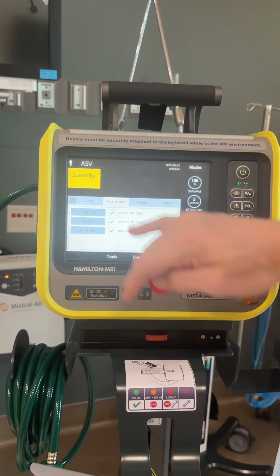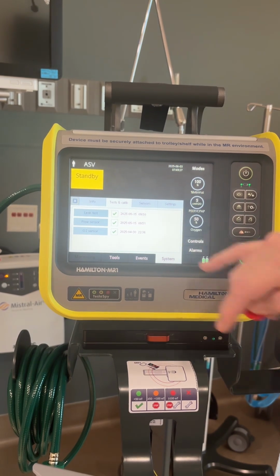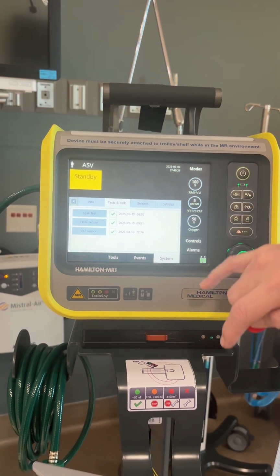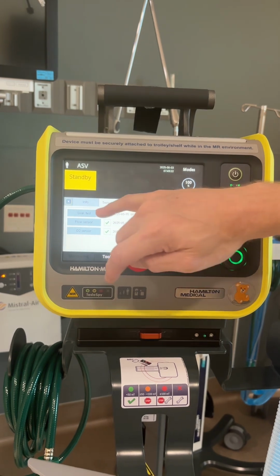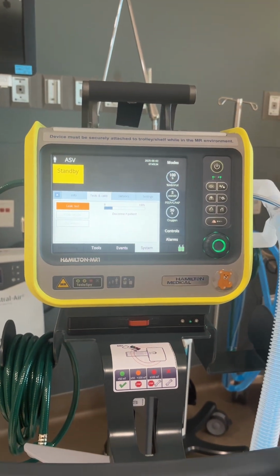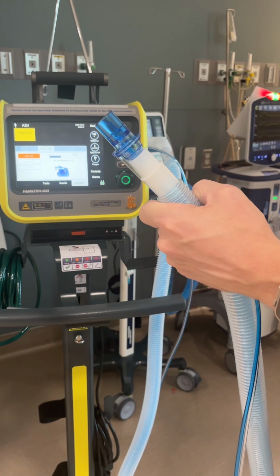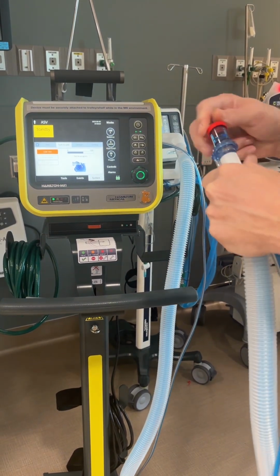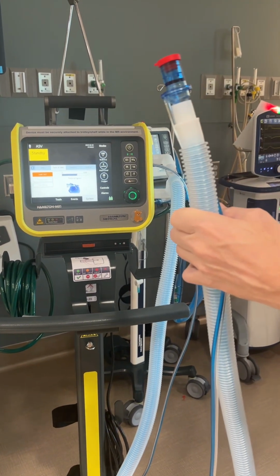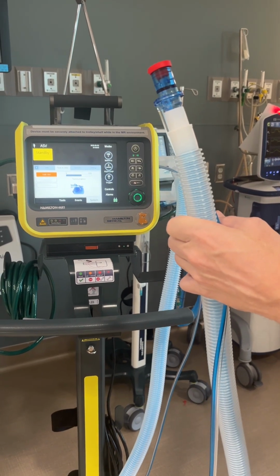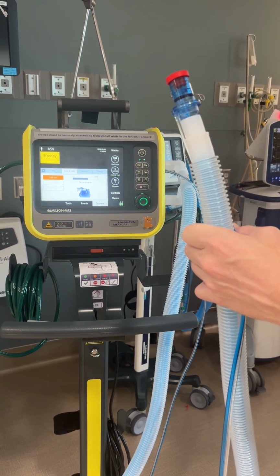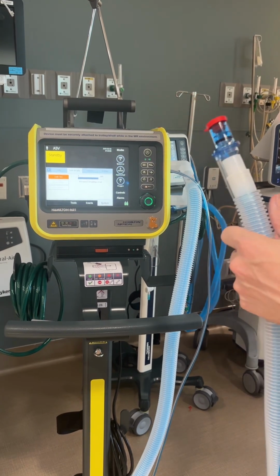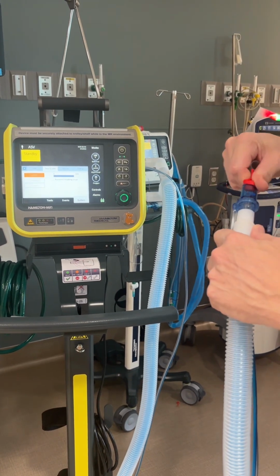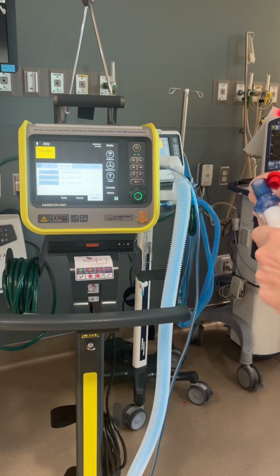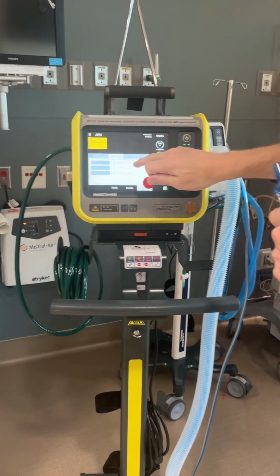The O2 sensor only has to be done once every 30 days. So you don't want to do that every time, because the O2 sensor only has a few different settings on there. So you're going to do the leak test right here. You're going to disconnect from the patient. You're going to block the breathing tube. You can use this. And then it's going to go through the leak test. And we reconnect the breathing circuit. You can take a look, and it's done. See how it clicked off here, the time right here.